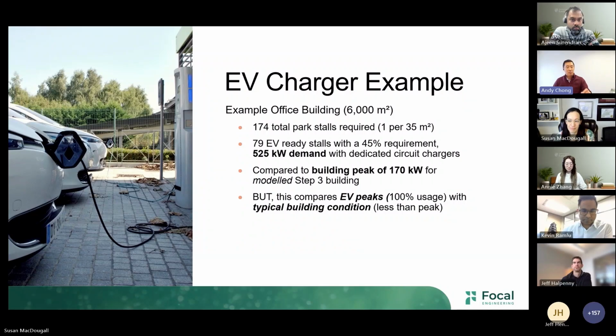And we're comparing it against an orange, it's an apple to an orange. That 170 kilowatt building demand is a peak of many different end uses that are fluctuating throughout the day. So we're not, for example, including the chiller running at full cooling capacity at the same time as our heating plant running at full capacity. Those things would never run at the same time. So we're looking at plugs, lights, heating, ventilation, and all these other things - we're chopping kind of a dynamic peak through that.